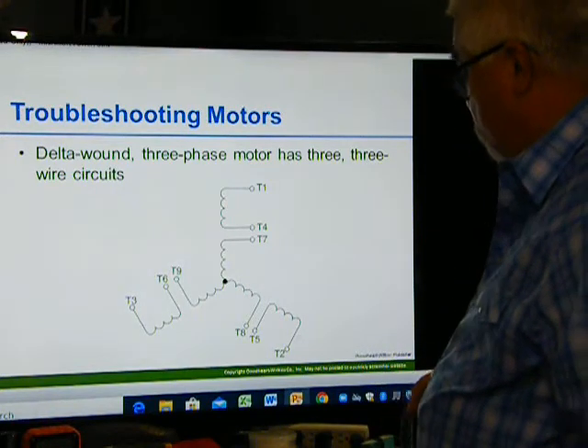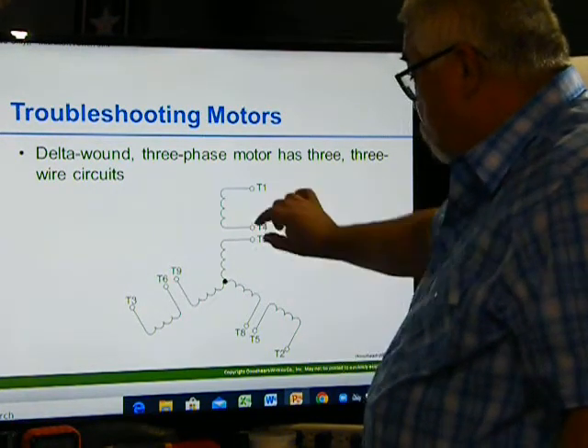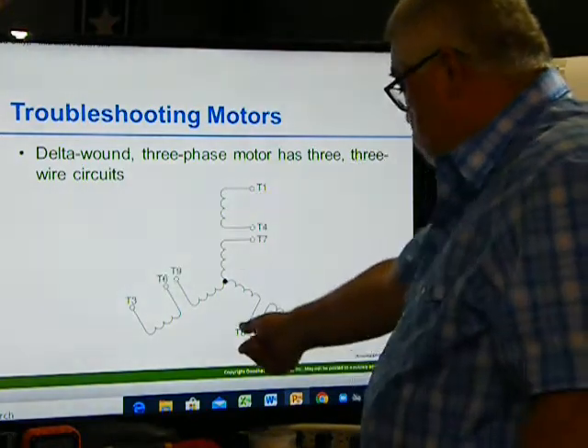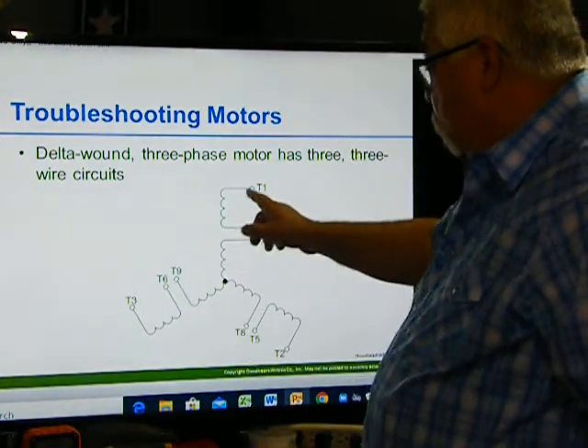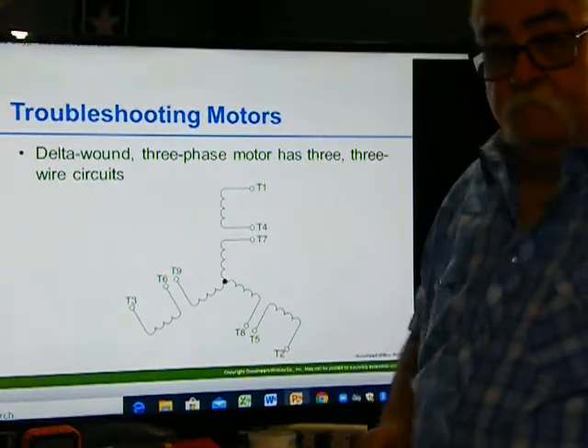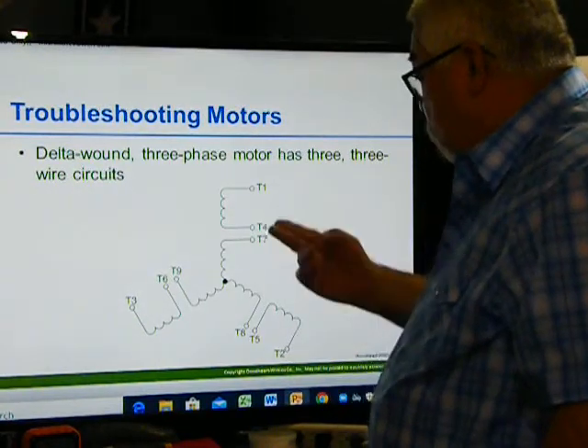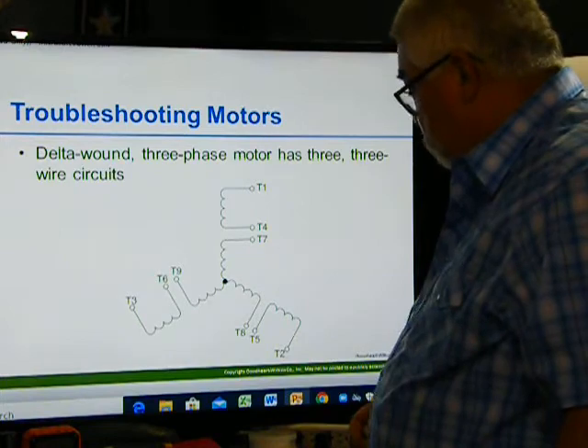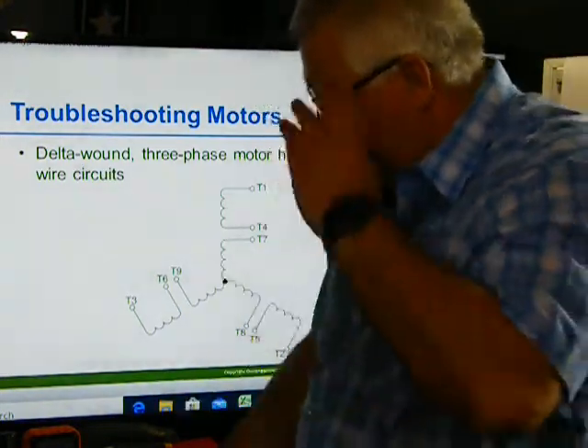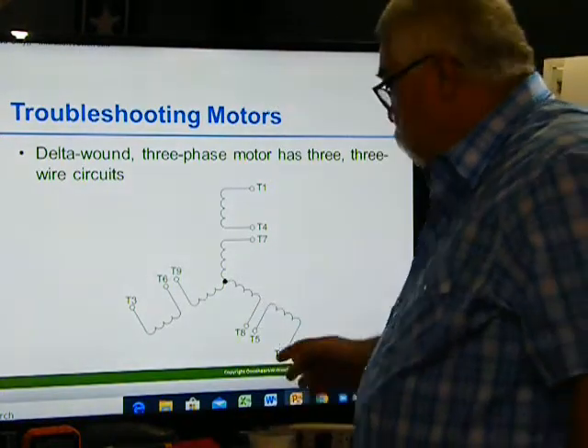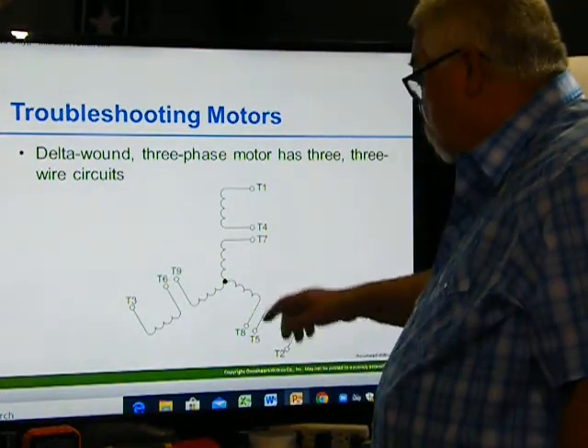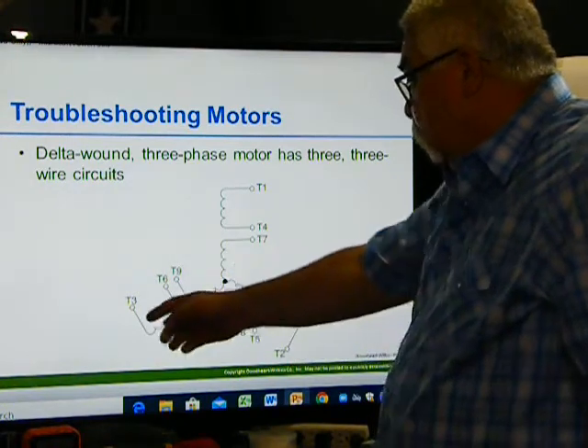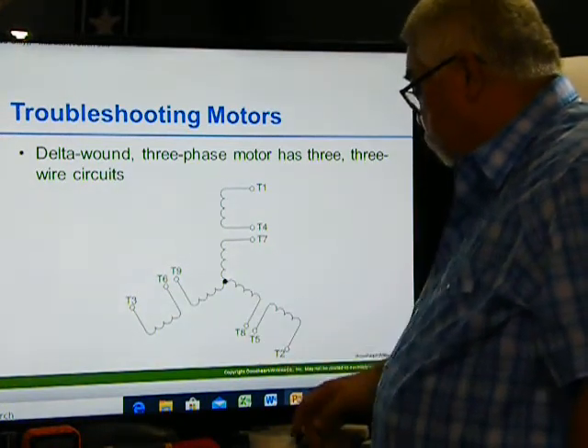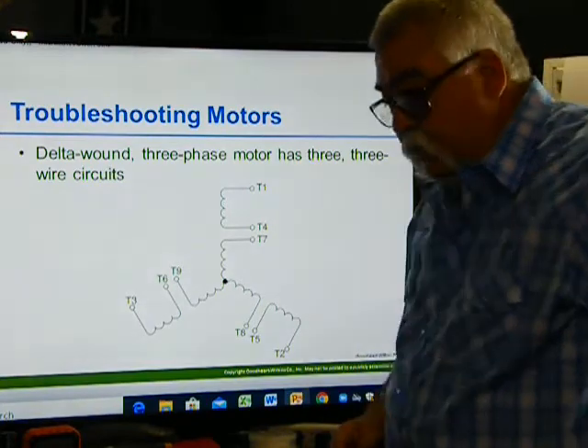So how's the voltage going to be? Sometimes we have the voltage coming in and we have a higher voltage. We're going to tie this here, and we tie in one hot here, one hot here, and one hot here. Okay, we have a different voltage, and then our leads change. I drew a blank on it right now, I'm sorry. So how we tie this depends on our voltage, but our leads and our windings, you can see they're all a multiple of 3: 3, 6, 9, 2, 5, 8, 1, 4, 7.